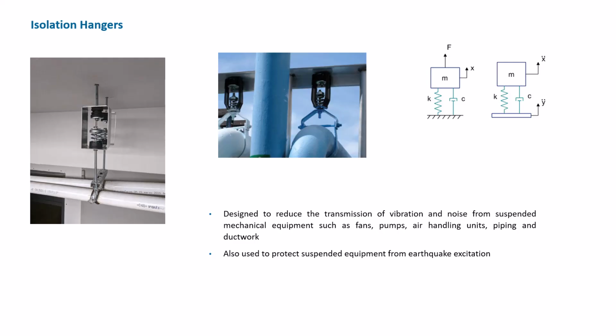There could be, for example, turbulent flows or vortex shedding in the fluids along those pipes. The idea is to isolate the pipes from the building structure to mitigate transmitted vibration from flow-induced vibration. But also, if the building is undergoing an earthquake, these same seismic hangers would isolate the pipes to mitigate their response to the building's vibration.